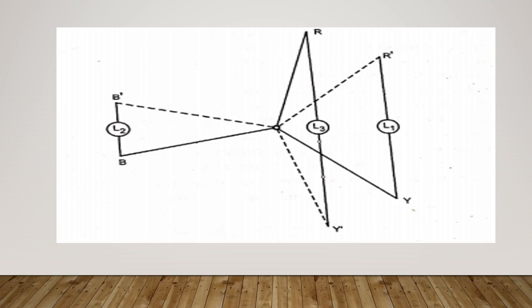If the incoming machine is too fast, then the phasor diagram R dash Y dash B dash will rotate faster than R Y B, so that the voltage across lamp L3, represented by R Y dash, will decrease, the voltage across lamp L1, represented by R dash Y, will increase, and the voltage across lamp L2, represented by B B dash, will decrease. And if the incoming machine is too slow, then R dash Y dash B dash will rotate slower than R Y B, so that the voltage across L3 increases, the voltage across L1 decreases and the voltage across L2 increases.